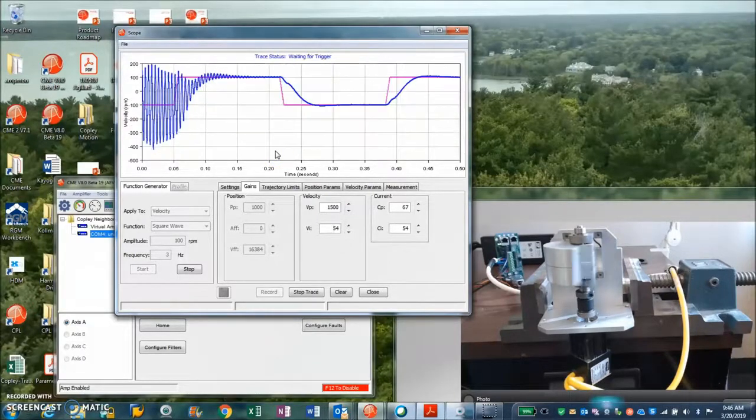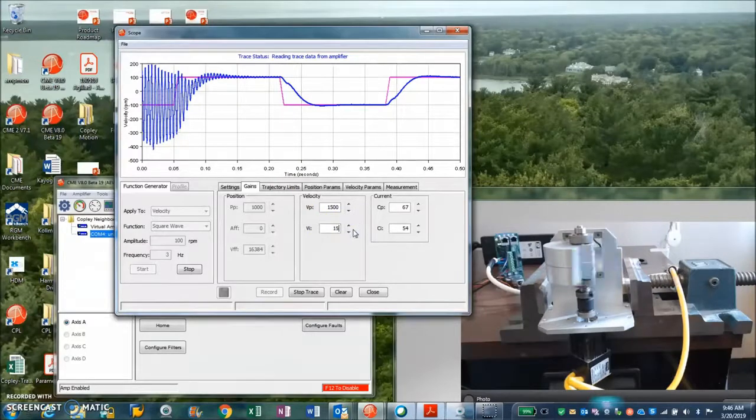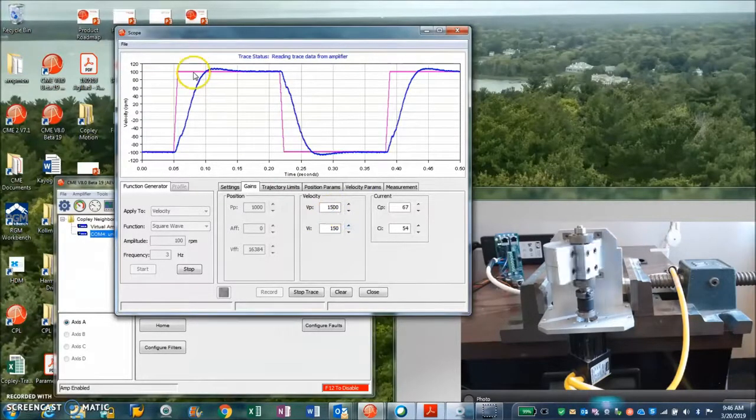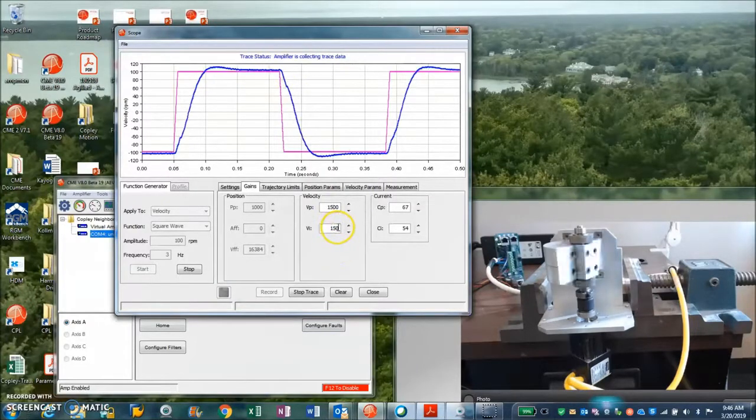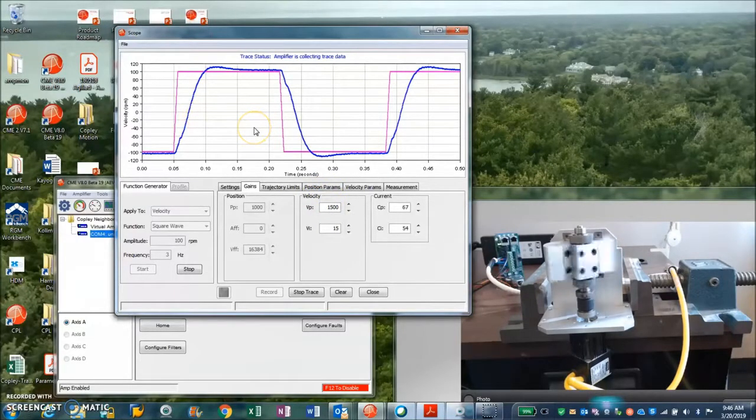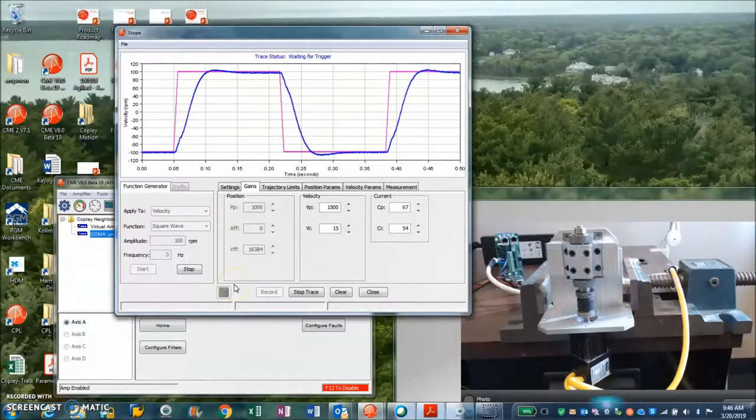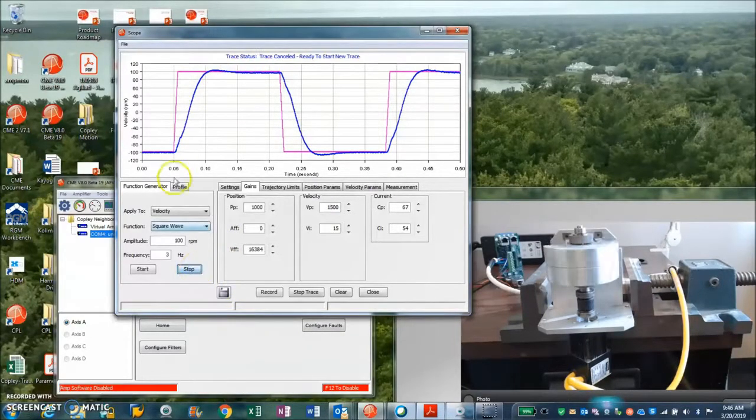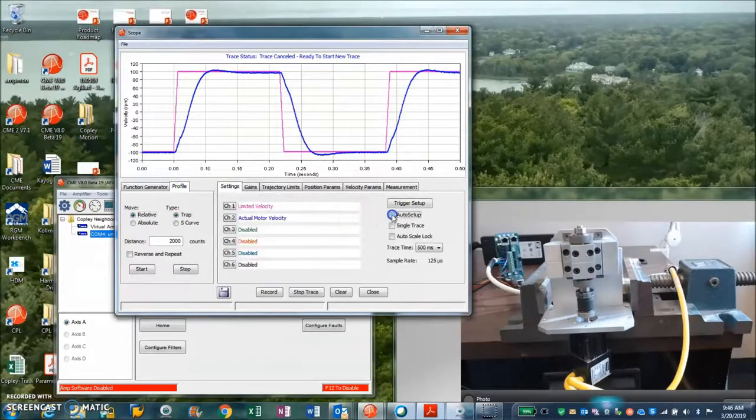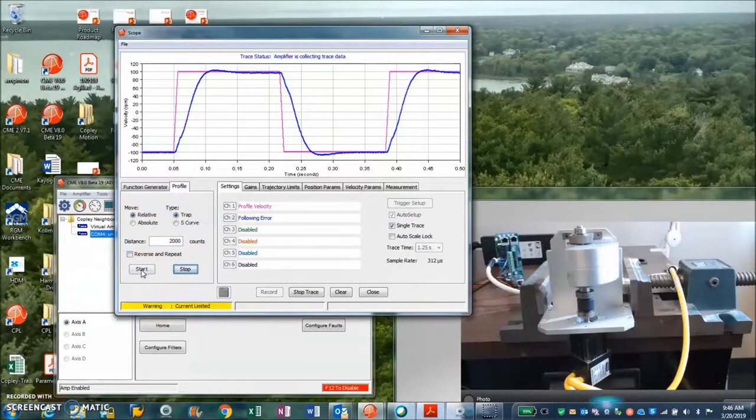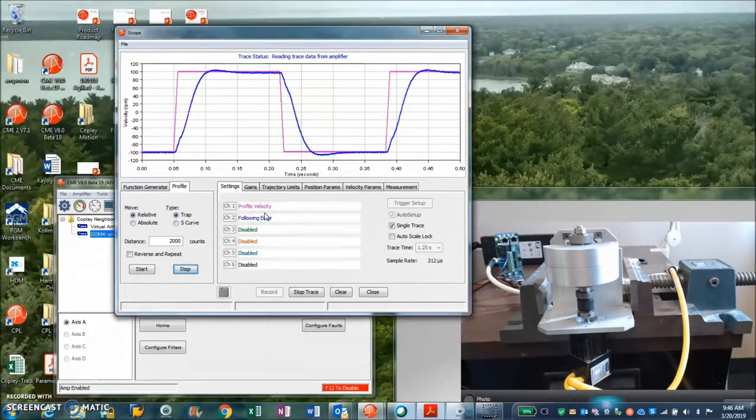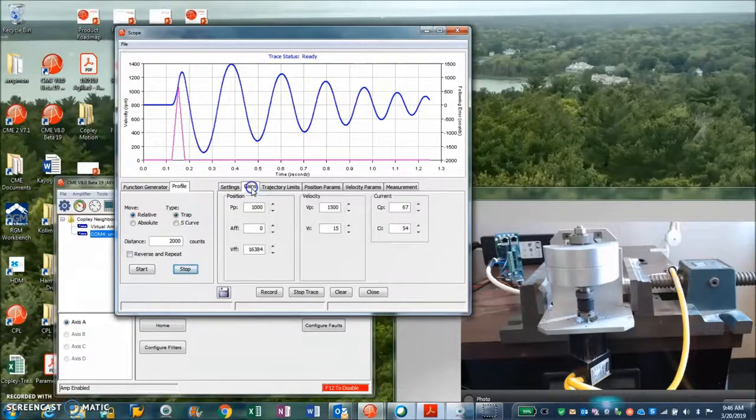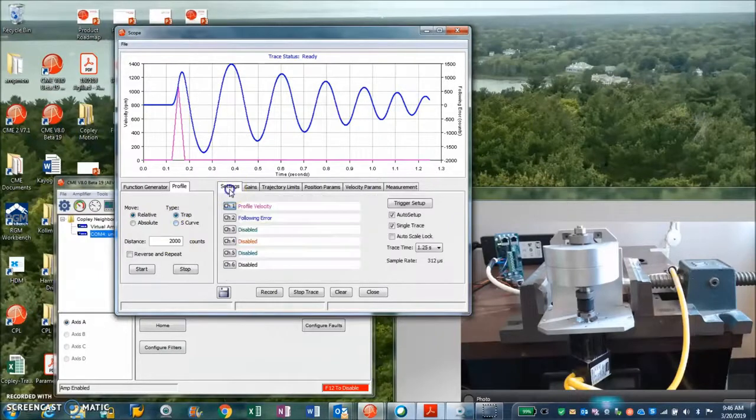If we look at the integrator, if the integral is too high, you get some integral wind-up. So there's the overshoot right there—it goes to steady state. So I'm going to knock that back down. Again, the frequency of the response is based on the stiffness of the velocity loop, and we pulled the pole in to 25 hertz, so that's pretty good. I'm somewhere in the range here. Now I'm going to do a little move in position mode. So again, the frequency is based on the stiffness of the velocity loop, and the amplitude is the proportional gain. So knock that puppy down there, make the move again.